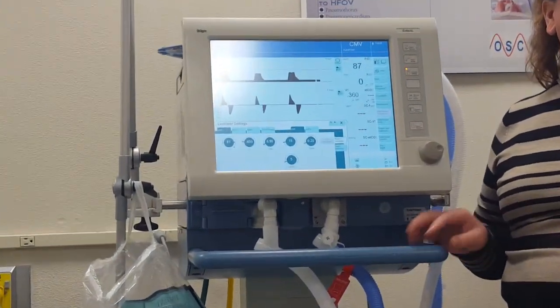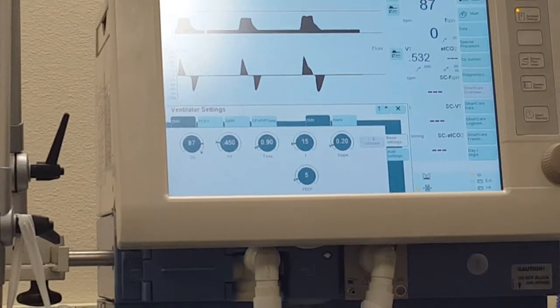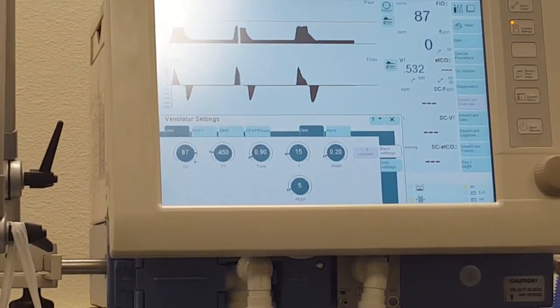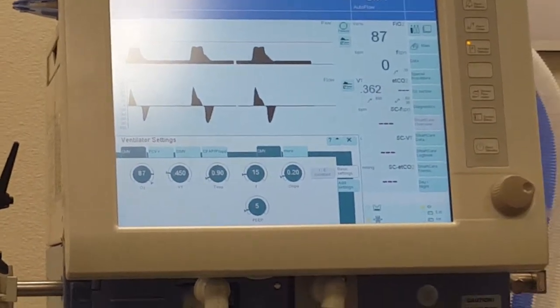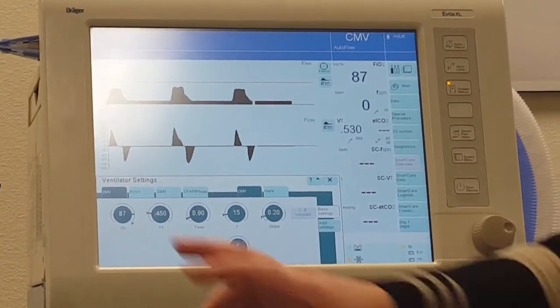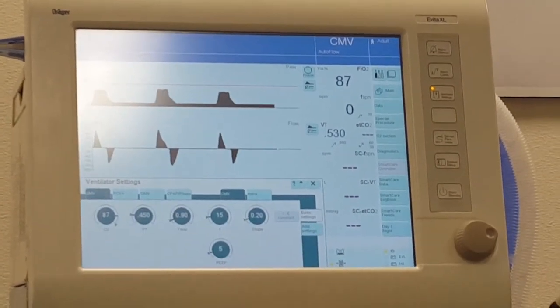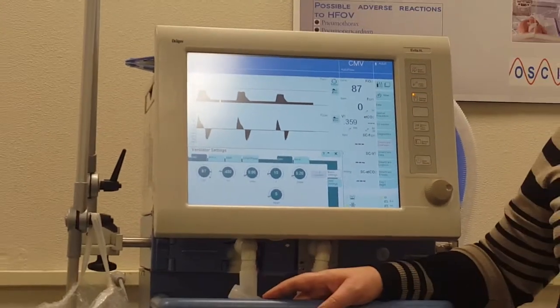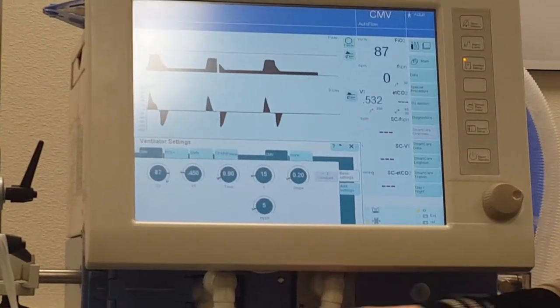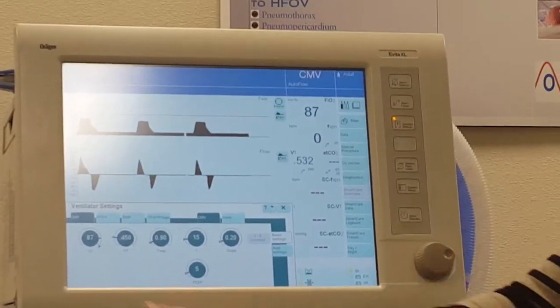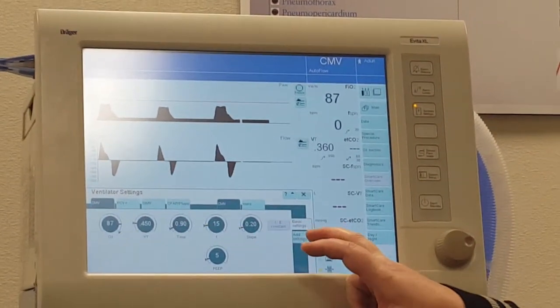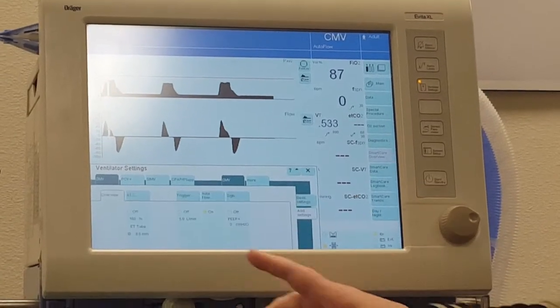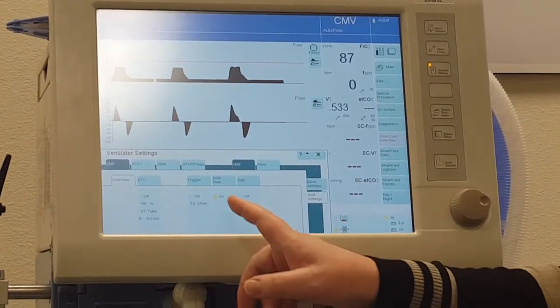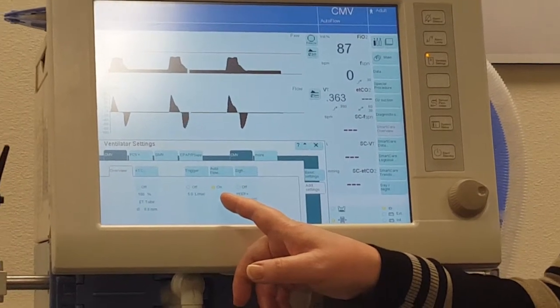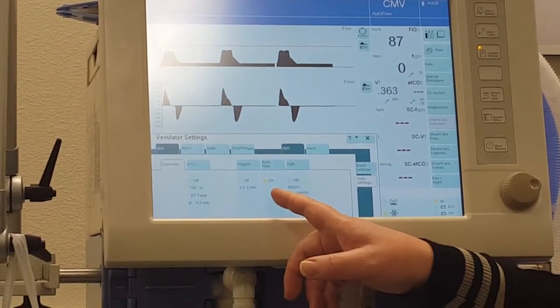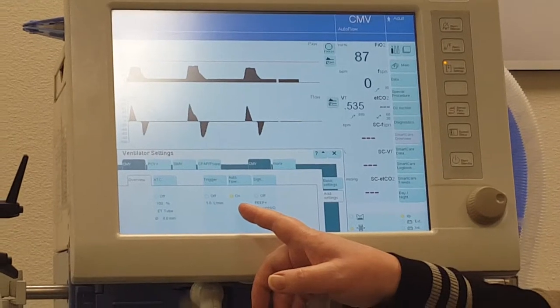Guys, we need to know about it. Okay, so if you want your patient to be in ACPRVC, you're going to go to CMV, and you're going to turn a setting called auto flow on, and it happens to be on right now. So if you go to CMV and then you go to additional settings, and then you'll see the word auto flow, you want it to be on. If you're in CMV and auto flow is on, you are in ACPRVC.